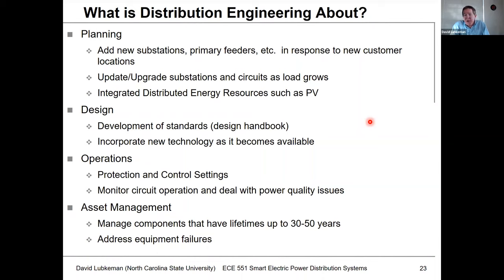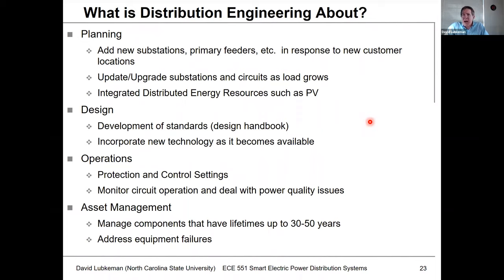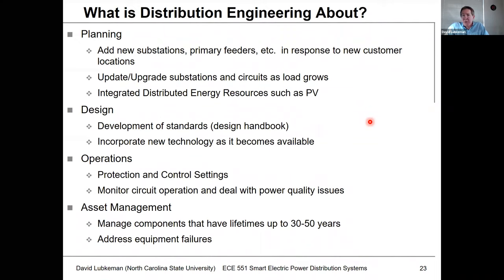Another aspect of distribution engineering is operating the circuit in real time. You need the right protection settings in your relays that control the circuit breakers, and control settings for voltage regulators and capacitor banks. You also have to monitor circuits in real time — customers may complain about voltage levels not being correct, or there may be unusual things going on with service.